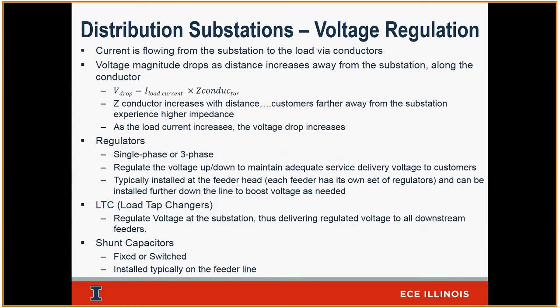All right. Voltage regulation. Any questions? Yeah. So when you said the fault current was about 4,000 amps, was it asymmetrical or symmetrical? Yeah, great question. So again, maybe that's why we need to dedicate a class for protection, talk about symmetrical components. And the 4,000 amps or 4,500 amps are typically symmetrical fault currents. You have a single-phase fault, two-phase fault, three-phase fault, and we'll talk about those, and we'll talk about what causes them, and again, the symmetrical characteristics of each when we talk about protection. But it's a fun topic to dive into. Yeah, the 4,000 will be a three-phase fault.